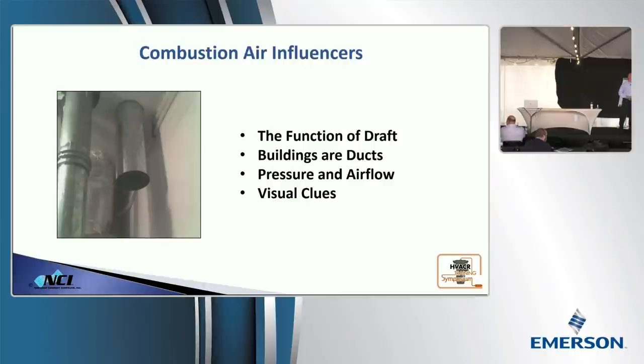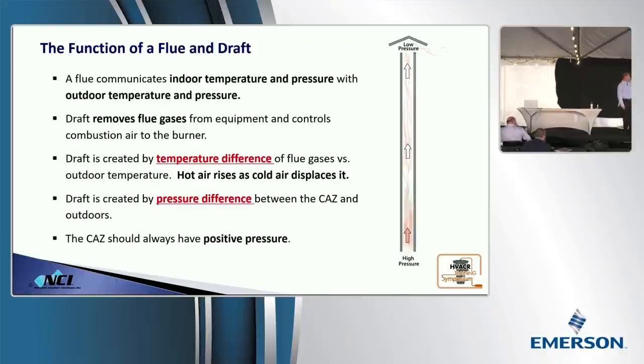And we're going to talk about buildings. Buildings are actually part of a duct system. There's two sides we're going to talk about. And we're going to look at the difference, and then we're going to see what we're assuming happens once we start punching holes in the walls or through the ceiling to see what happens. Then we're going to get into some very fundamental elements of pressure and airflow, and we're going to tie every single one of these into combustion air so you can see what's influencing these. And then I'll give you guys some visual clues to look for. You've probably been seeing this stuff all along and been going, oh, that's what's causing that. So I'm hoping that there's some big aha moments as we go through this section.